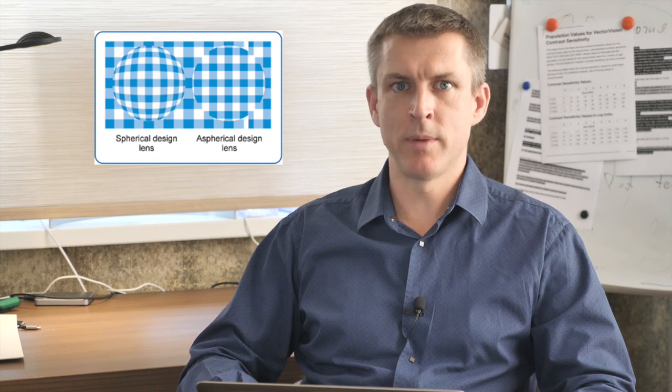Single-piece IOL with diffractive aspheric optic. The most important here is asphericity type. Spherical IOLs tend to have less quality of vision, especially in dim light conditions, while aspheric optic has better quality. There are different asphericity types available: zero asphericity and negative asphericity. Generally, if we're talking about average cornea, the more negative asphericity we have, the sharper and brighter image in terms of contrast we will have on the retina. Alcon Panoptix has an average amount of negative asphericity.